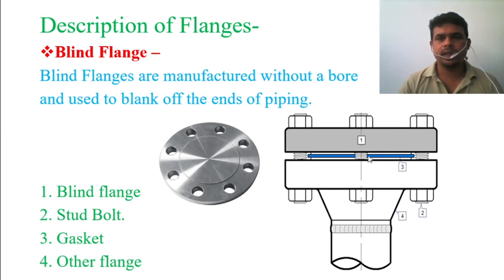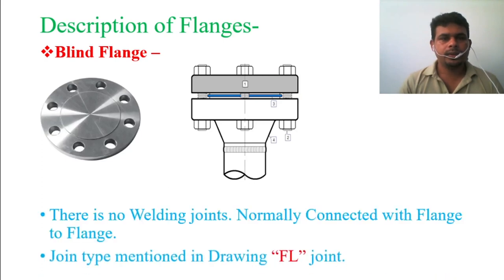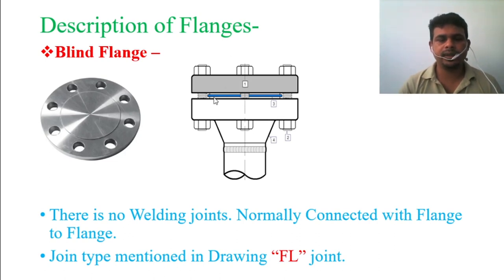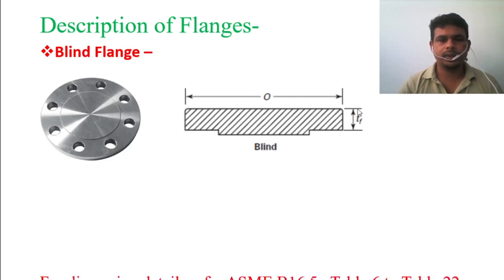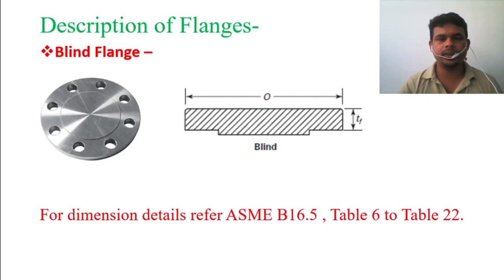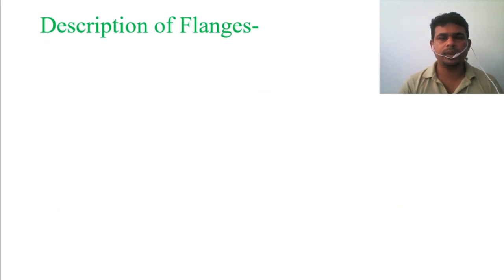You need two flanges to connect — as shown in the first lecture, this is how you connect a flange. For the blind flange, there is no welding joint; it is normally connected flange to flange. The joint type mentioned in the drawing is 'FL', which indicates a flange-to-flange connection. For the blind flange dimensions — outer diameter and thickness — refer to ASME B16.5, Table 6 to Table 22 and ASME B16.47 for larger bore diameters.